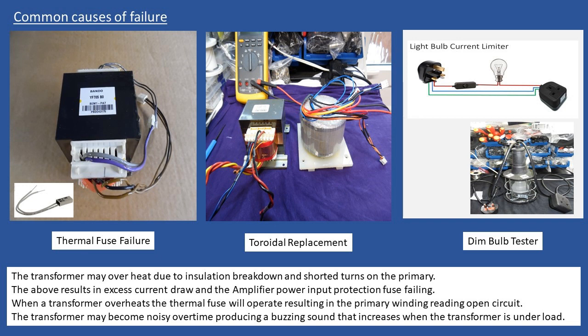So it could cope for short durations, but if it's on for maybe 4 or 5 hours of very, very high volume, with the transformer working very, very hard, you could find that the transformer overheats and then it fails. The other common cause of failure is it just fails, right? And you might say, well, what do you mean just fails? Well, anything that is manufactured, and if you think about the enamel wire, you would hope that the enamel coating, when it passes through the dryer, is even throughout, but sometimes it just isn't. You might have a case where it's thinner in some areas and thicker in others, and then the net result is that it just fails. Okay, so that's covering the thermal fuse part.